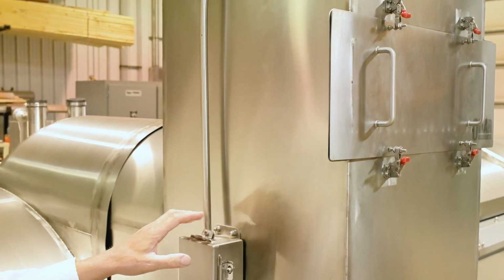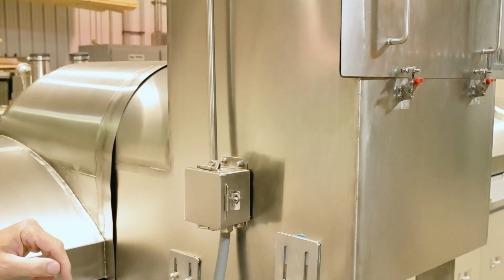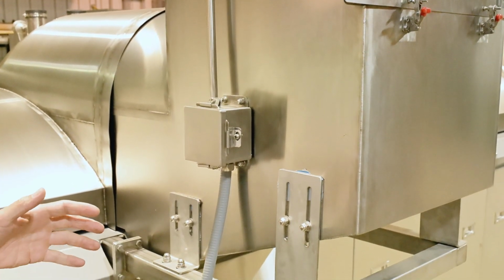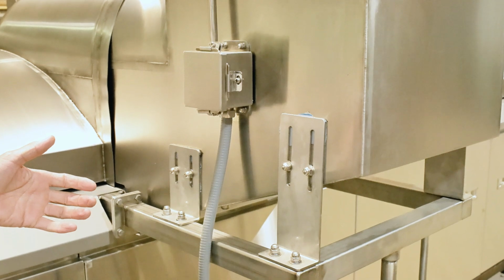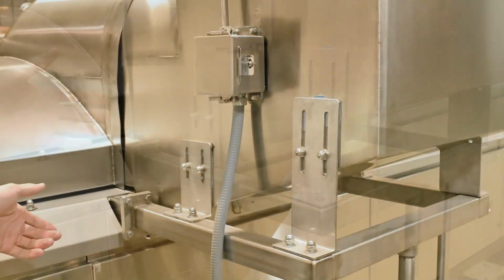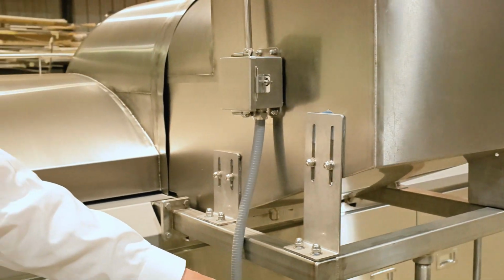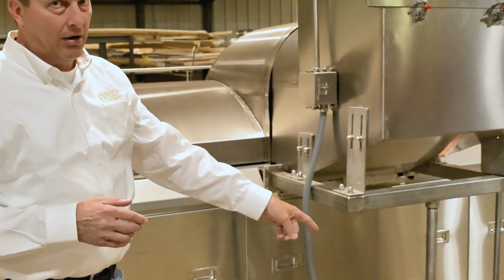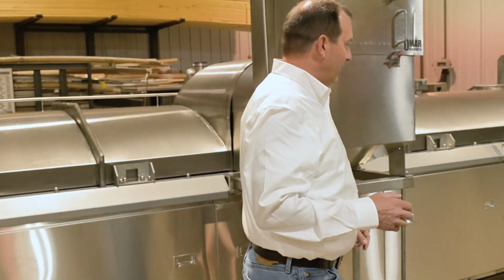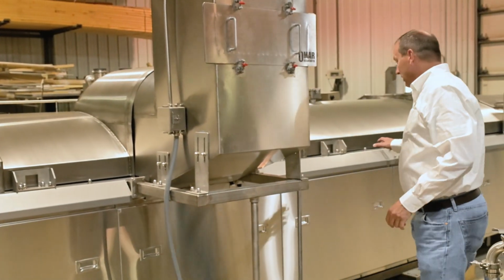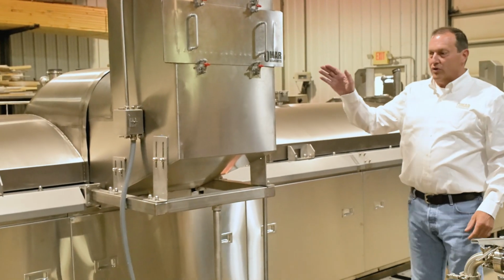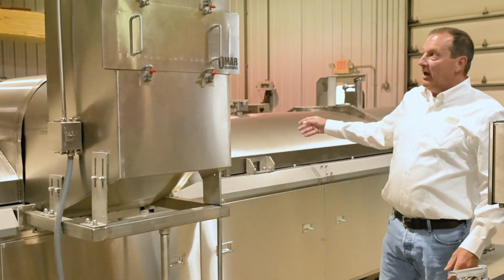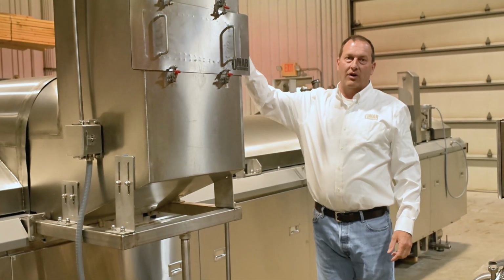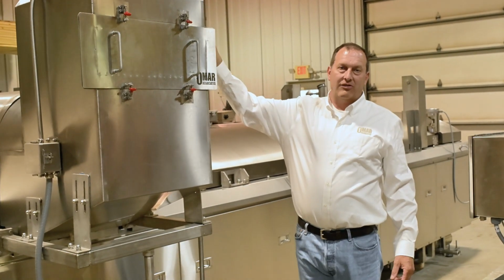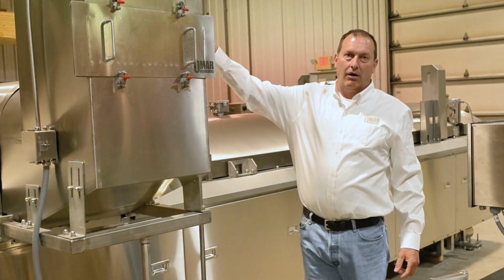The system is pre-piped for CO2. All we have to do is add an off-machine supply system, connect it to the pipework that's already on the fryer. So there are release nozzles inside the fryer tank. There are two in the fryer tank, and there are two more nozzles in the steam vent. Those are all pre-piped, standard feature of the Omar fryer.